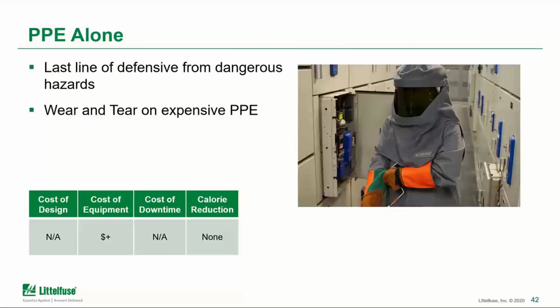And PPE alone is worthy of mentioning here, just as a conversation point, that it's not really an effective solution for mitigating arc flash hazards as the only method. It's really the last line of defense from arc energy. So with the PPE, although the cost can be reasonable and it's still something that needs to be in place for each of the employees to work on the equipment, it's not something that is really in place in the equipment to provide permanent arc mitigation.